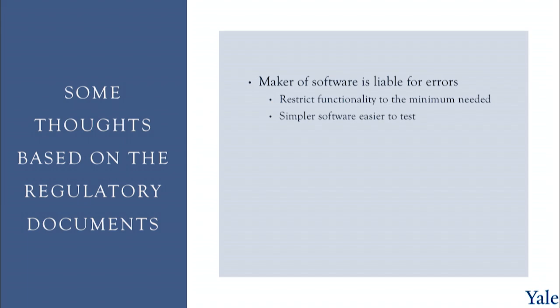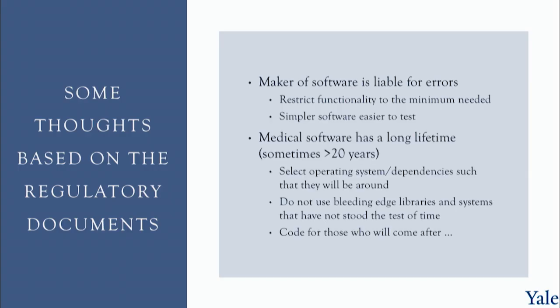To conclude: the maker of the software is liable for errors, so we should restrict functionality to the minimum needed — simpler software is easier to test. Also, medical software has a long lifetime, sometimes more than 20 years, so select operating systems and dependencies that will be around. Avoid bleeding-edge libraries that haven't stood the test of time. Code for those who will come after you — prioritize clear designs and clear code, even if it means sacrificing a little efficiency, to make the software easier to maintain over time.